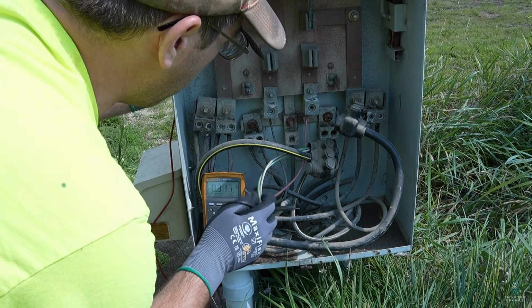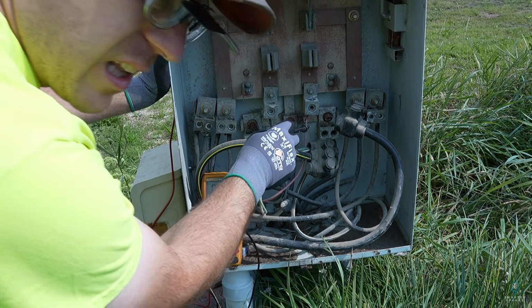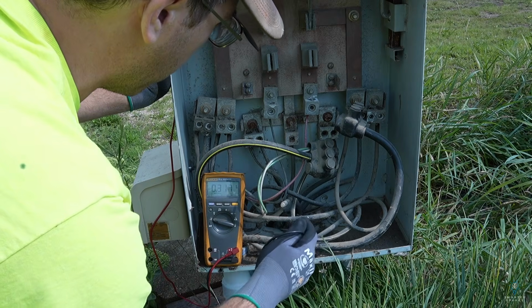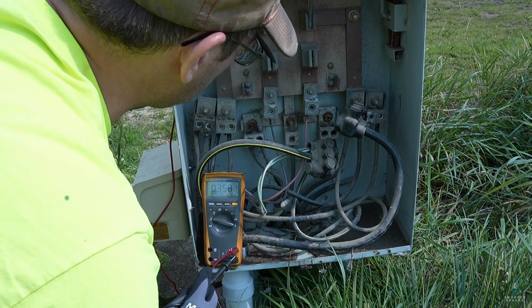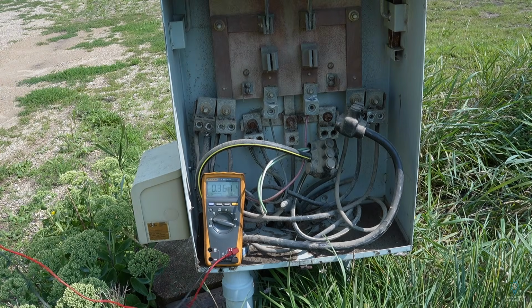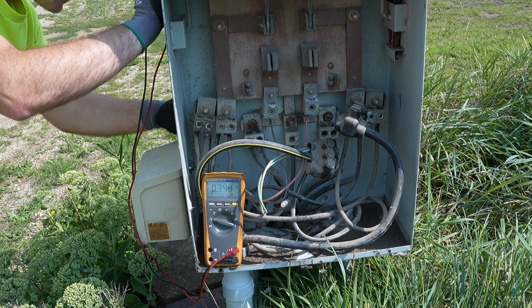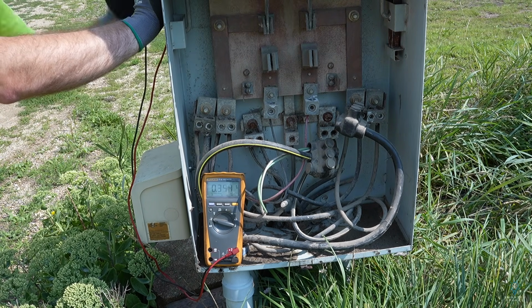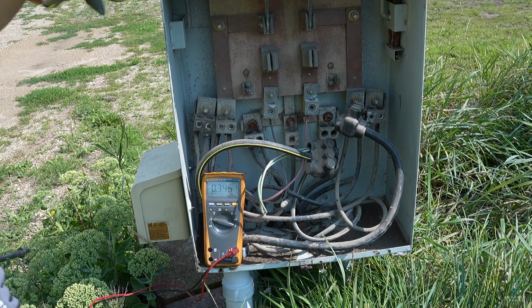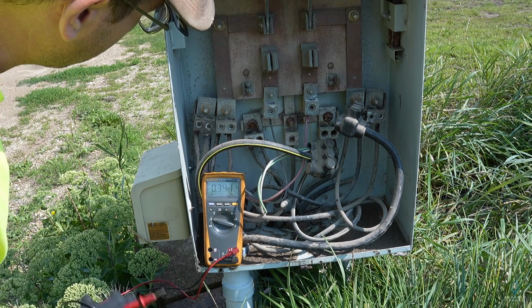Yeah, there is major corrosion on that lug that neutral is fed from. That lug just might need to get replaced. Can I see those bolts on the back? I can. So I could replace those lugs if I had lugs.